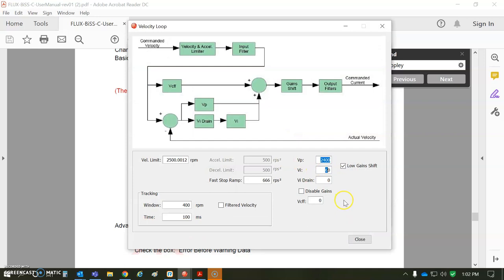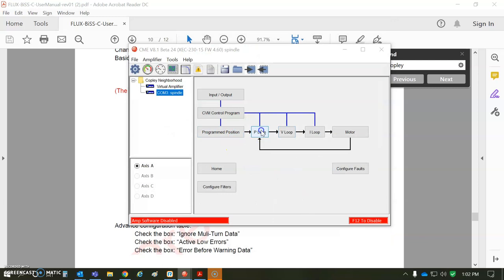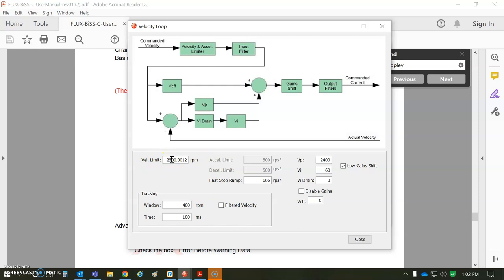Position loop is all tuned up. So now that we can hit the desired—I need to go 2500 or less. This number must be 10 or 20 percent greater than anything you want to do. We can make a move now in position mode. A thousand RPM, under 100 for accel and decel. Let's make a move.